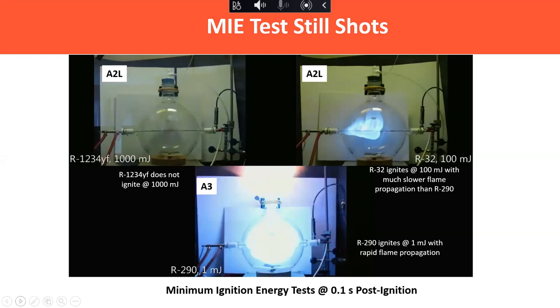And then over on the upper left, you can even go up to 100, 500, even up to 1,000 millijoules, and you do not get ignition of the 1234YF. So again, a good visual and measurable demonstration that there are real differences between the class 3 flammable refrigerants and the 2Ls. So next chart, please.